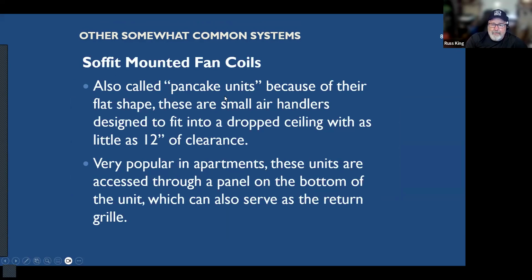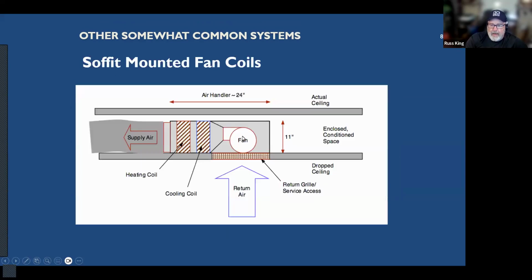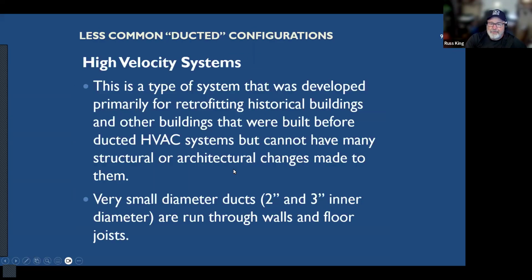Soffit mounted fan coils are the pancake units. Let me show you a diagram. They only need about 11 or 12 inches of a drop ceiling, and it mounts up in there, and then the ducts can go through that drop ceiling and get to where they need to go. Sometimes the return is right in the bottom, so there's a return grill in the bottom of the unit. You take a couple screws out, you take the return grill off, and you're looking right up inside the fan coil unit itself. Very common in apartments, very common in larger hotel rooms. We'll have these in them. So soffit mounted fan coils, ducted mini splits.